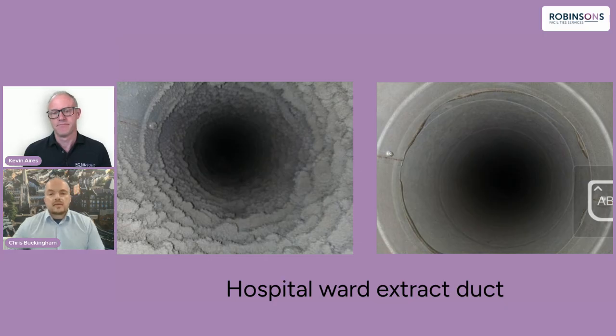It could be multiple things. Heat is a good one - if you walk into a room and it's a lot hotter than another room, say in a large office block, that heat could be a sign the ventilation isn't working correctly. Smell could be another - a dust odor, and if any moisture gets into that dust you get a sludginess, which gives off a smell. Dust itself is a sign too - next time you're out, look up at an extract grill and you'll generally see dust around the edges, sometimes even inside. All of that is a good indicator the ventilation isn't in the best condition.